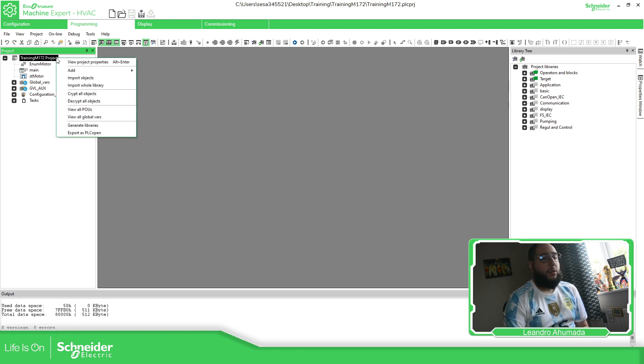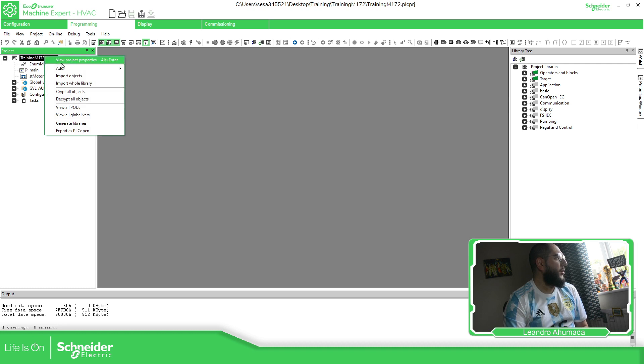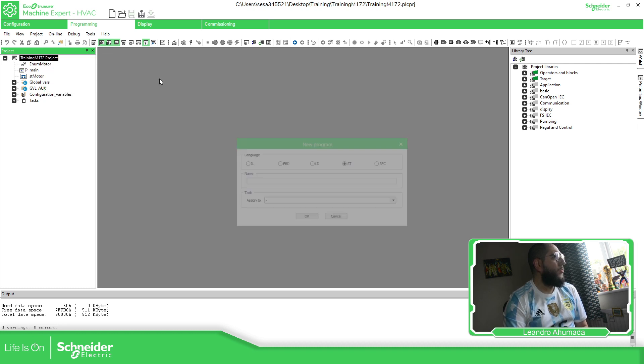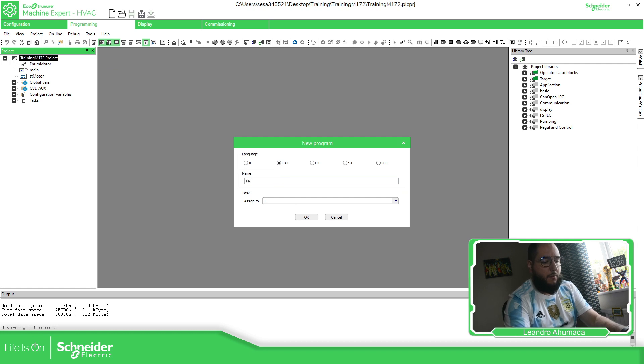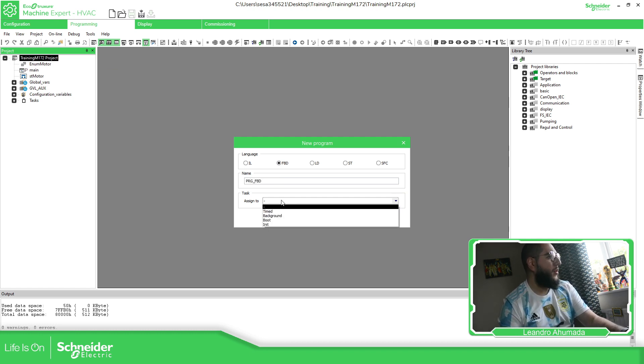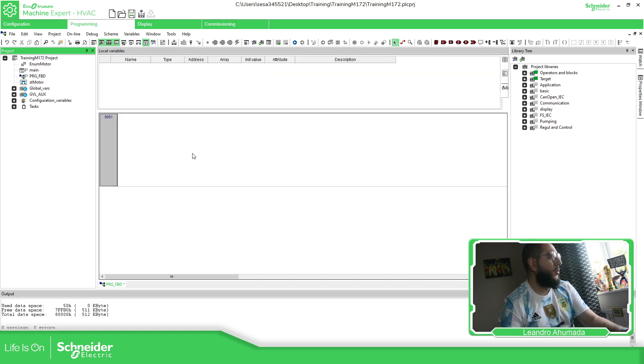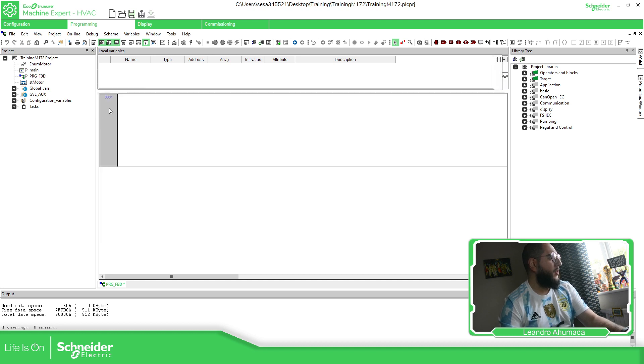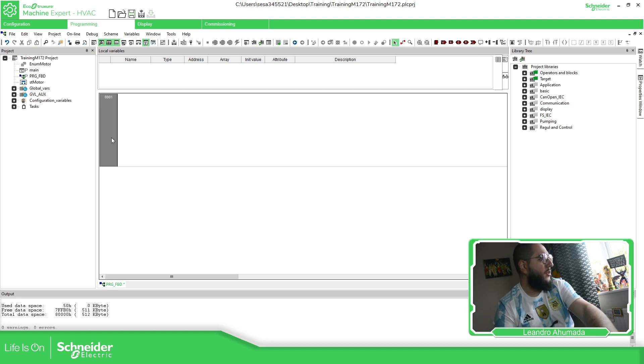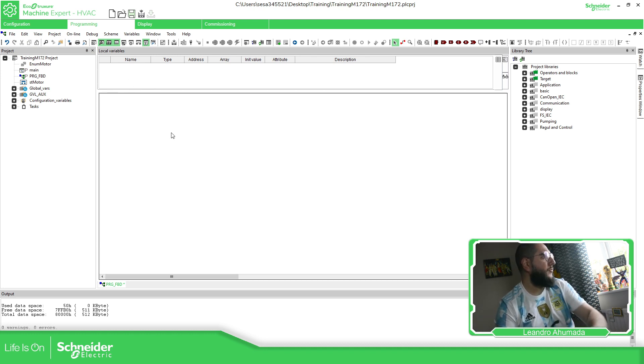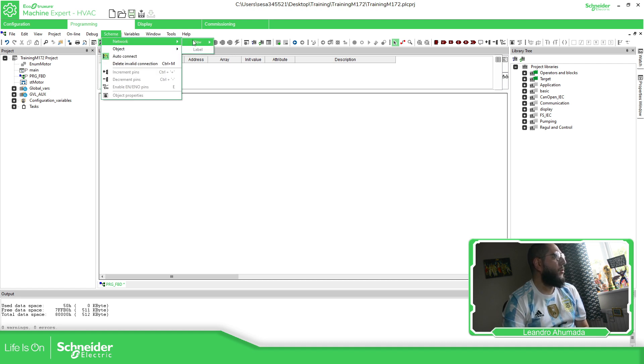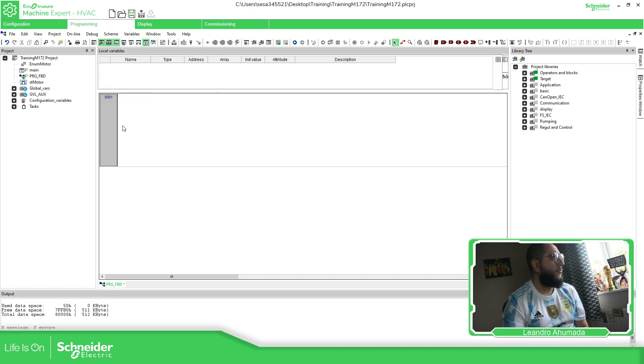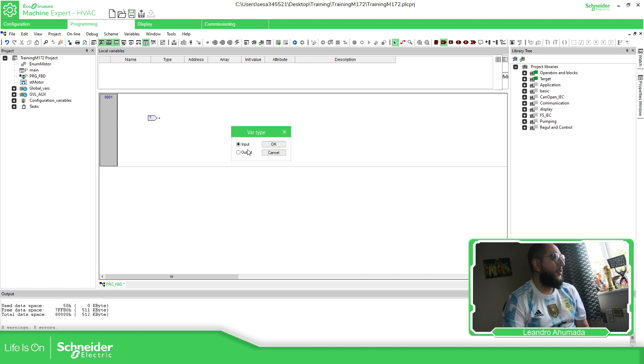In order to add a POU FBD, right click over here, add new program FBD. So I'm going to put PRG_FBD. We just need to define the task that we're going to add it. And then we have this. You can see here, right click new network and add another one, otherwise I can delete it. And if I delete it, there is no right click here. So we just need to go Scheme, Network, New, and then just any of this to add a new one. Now you can add this here, input and output.